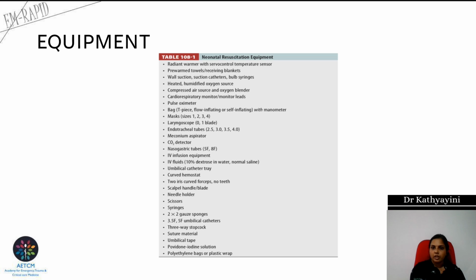Then, if at all required, we'll have to go for an intubation. For that, we'll require a laryngoscope, preferably a zero or one size straight blade. Then ET tubes will be required, of size 2.5, 3, 3.5, or 4. Then meconium aspirator, ETCO2 detector. Then nasogastric tubes will be required. Then for securing IV access, we'll require IV cannulas. Then IV fluids will be required: 0.9% normal saline, or if the baby is having hypoglycemia, we'll have to correct that, so 10% dextrose will be required. Then we may have to go for umbilical vein cannulation. For that, we require umbilical catheters, three-way stopcock, suture material, umbilical tape, all these things will be required. Apart from that, other emergency drugs like adrenaline, all those things should be made available in the neonatal resuscitation area. So equipments are very important in a neonatal resuscitation because all these things should be available.